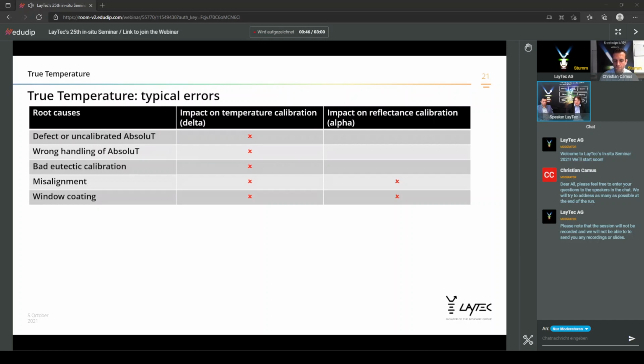It's important to monitor the effect very carefully, because in worst cases, and Oliver can confirm that we have seen viewports almost completely black from almost complete deposition. In such a worst case, the dampening factor to the light transmissivity is extremely high and can affect both the delta calibration for temperature calibration as well as the alpha calibration factor for the reflectance calibration.